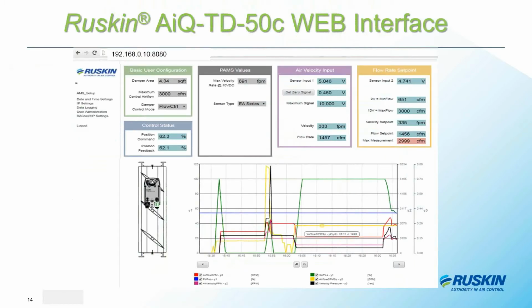So what we're looking at here is the IP address at the top. You would log on using, in this case, 192.168.0.10:8080, and that puts us right into the actuator. And then the login is admin and the password is in the instruction manuals. Now, you're not all writing this down, but it's in the instruction manuals as well that will come with the product. And this is the screen that will come up, what you'll see as soon as you log on to it.